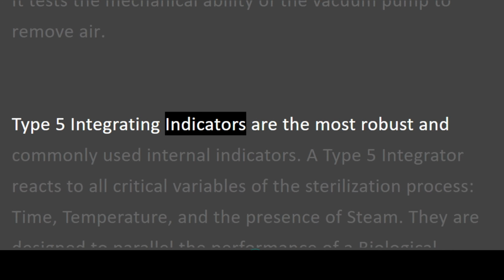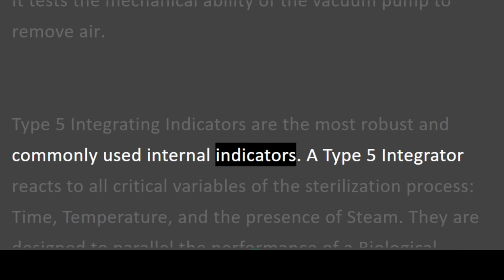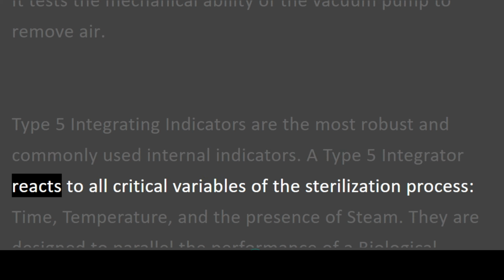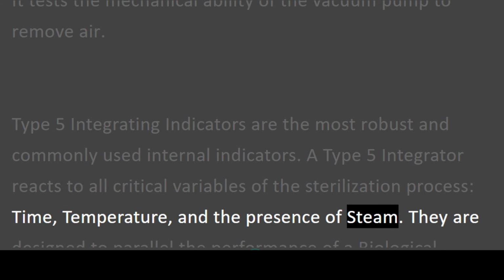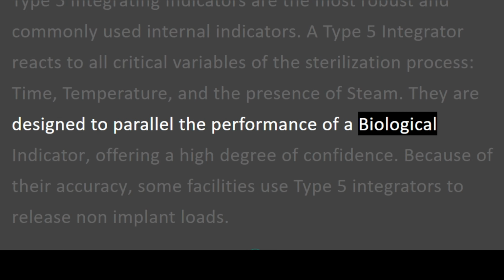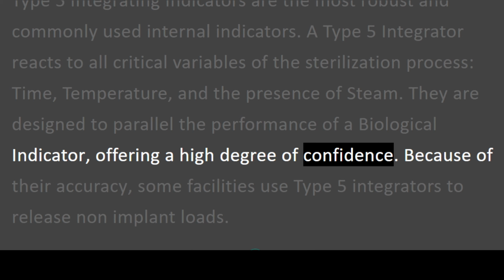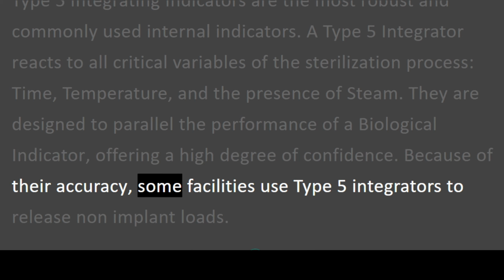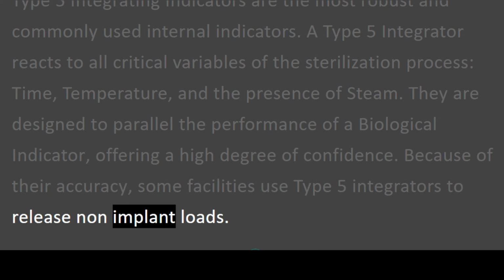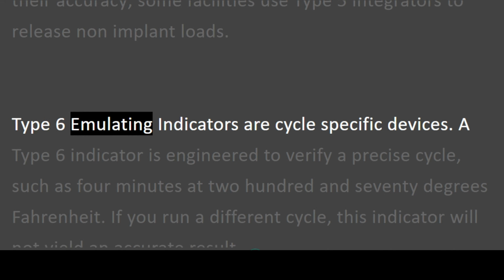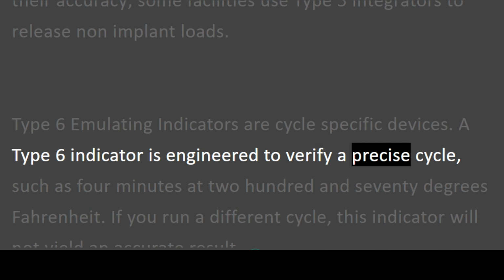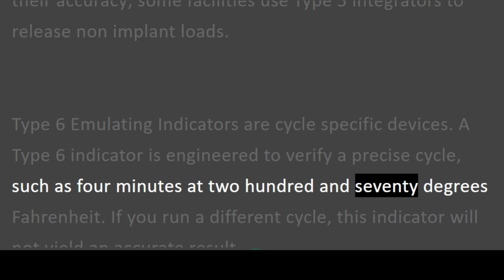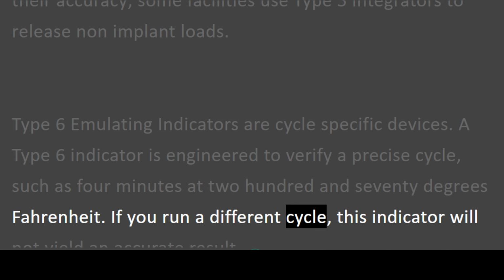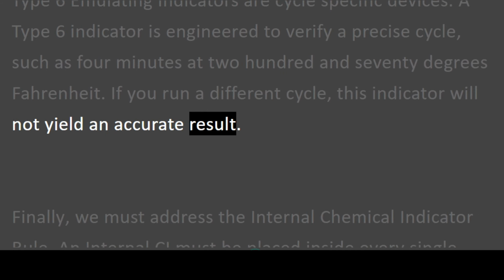Type 5 integrating indicators are the most robust and commonly used internal indicators. A Type 5 integrator reacts to all critical variables of the sterilization process: time, temperature, and the presence of steam. They are designed to parallel the performance of a biological indicator, offering a high degree of confidence. Because of their accuracy, some facilities use Type 5 integrators to release non-implant loads. Type 6 emulating indicators are cycle-specific devices. A Type 6 indicator is engineered to verify a precise cycle, such as 4 minutes at 270 degrees Fahrenheit. If you run a different cycle, this indicator will not yield an accurate result.